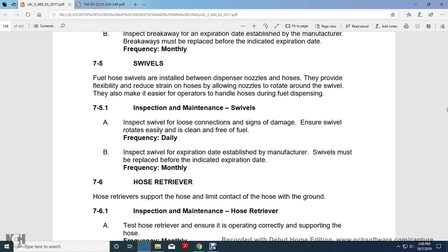Inspection and maintenance, swivel. Inspect the swivel for loose connections and signs of damage. Ensure the swivel rotates easily and is clean and free of fuel daily. Inspect the swivel against the expiration date established by the manufacturer. The swivel must be replaced before the indicated expiration date, monthly.